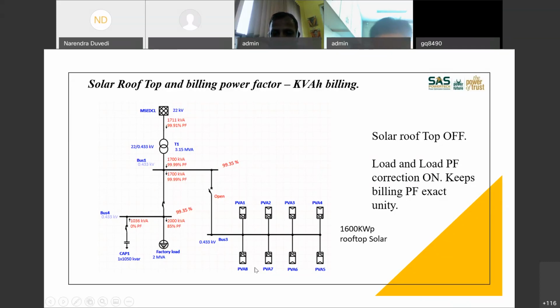At present, you can see that the 1600 kWp is disconnected from the grid, and I have compensated the power factor totally. So my load is drawing 1700 kVA at 99.99% PF, and I am drawing 1711 kVA at 99.91 PF from grid. So this is my ideal situation, almost unity power factor. Solar is not supporting anything at present. Now let us go to the next slide.